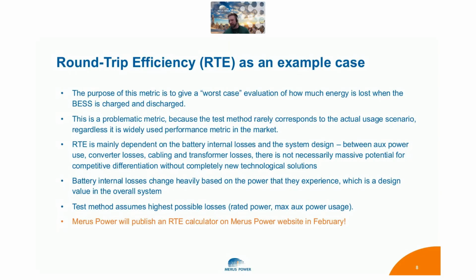deeply. RTE is really mainly dependent on the battery's internal losses in different operation points, because if you think, let's say, a high voltage connected energy storage system at 110 kV, what causes losses in the powertrain are transformers and cables that are, as you can imagine, pretty much the same for all suppliers. Power conversion system, where there's some difference in the efficiency. But finally, I'd say 60-70% of all the losses are always caused by the internal heat losses of the battery, which are heavily dependent on the system design, power energy relationship, settings for the battery, HVAC or chillers, and so on. Therefore, one number for RTE doesn't really tell much about how well the system is designed.